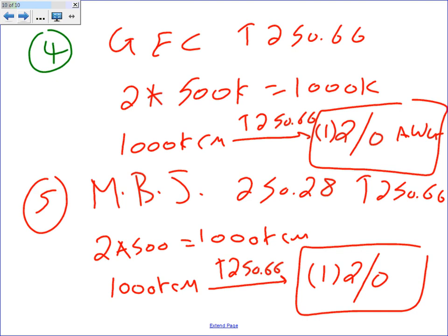Longer. What is that? Yep. 2A, 2 times. I don't know who wrote the A. Give me the code number for your neutral calculation. 250.61, I'm sorry, 220.61. Right. The one I'm reading on 220.61 just multiplies it by 0.7. Yeah, that's what we did. Now we took 200 out first.